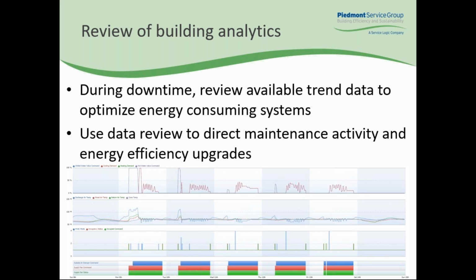As an example, using trend data from our building analytics platform for a facility that has three 80-ton package rooftop units with demand control ventilation, I recently found three combination thermostat CO2 sensors that had failed for one of the rooftop units. They were stuck at a CO2 reading of 1,150 parts per million, which is probably about 350 parts per million above what would be considered comfortable, which was causing the rooftop unit to provide maximum outdoor air.